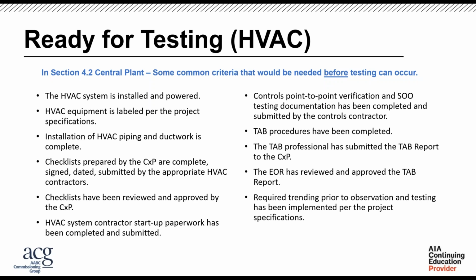Are we meeting those CFM guidelines? Are we meeting that design set point? Or are we off? If we're already off before we get to the testing, then testing's not adding as much value.